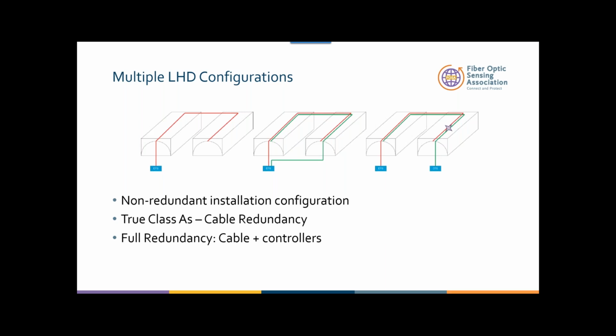At the end of the day, if you have a break within a cable, you can still monitor up to that point, and you have no loss in your fire detection and alarming system. This is just amazing from an engineering and fire detection point of view: the asset is still being monitored up to that point, regardless of the problems or the fiber break.